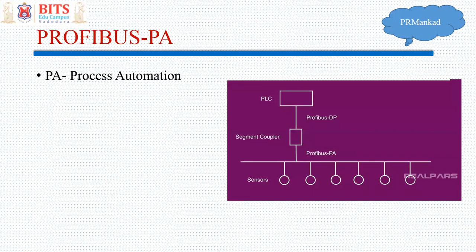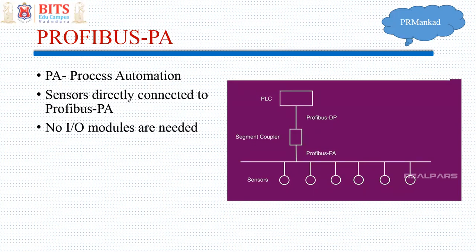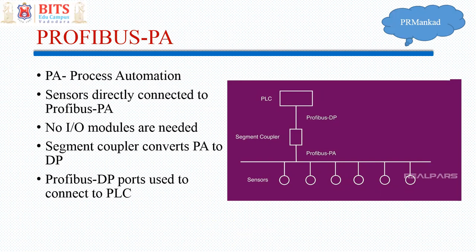Profibus PA stands for Process Automation. Here the I/O module is removed — sensors are directly connected to Profibus PA with no I/O module required. If your PLC is older, you can use a segment coupler which converts Profibus PA to Profibus DP, allowing compatibility with older PLCs. Profibus PA is the latest variant of Profibus.